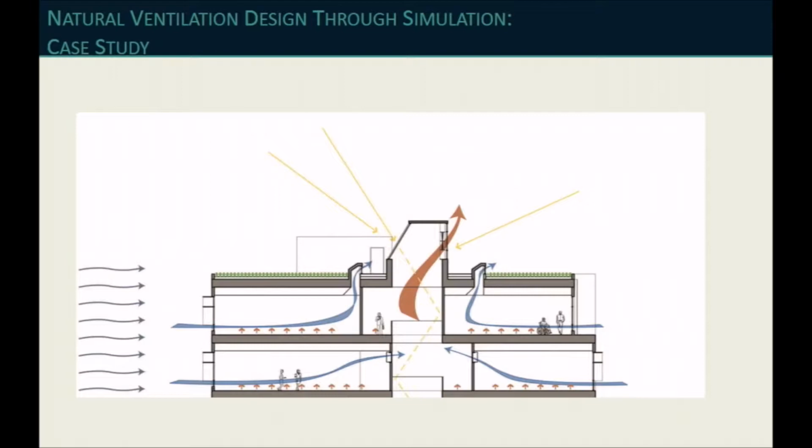So the question that I was tasked with answering was, how big should the louvers be on this project? Because they're going to use up wall area. They're opaque, right? So you're eating up area you could use to put windows and daylight the space better, and it also affects the look of the exterior of the building.